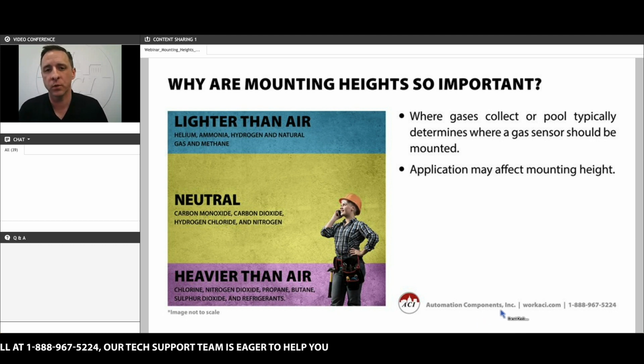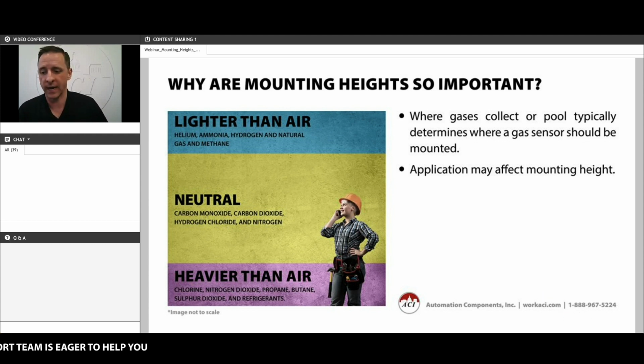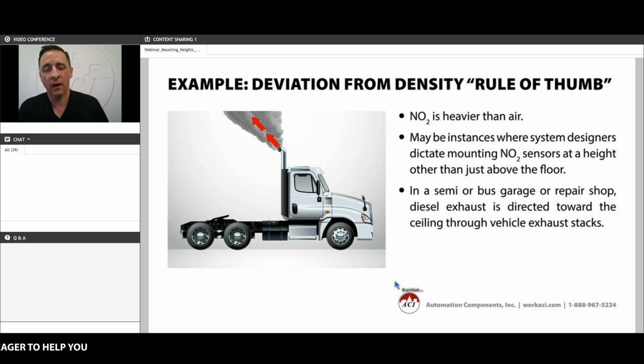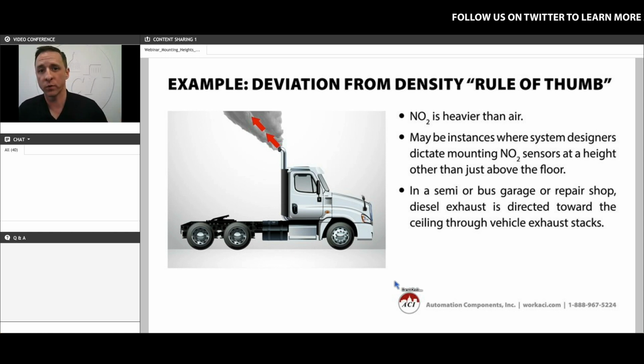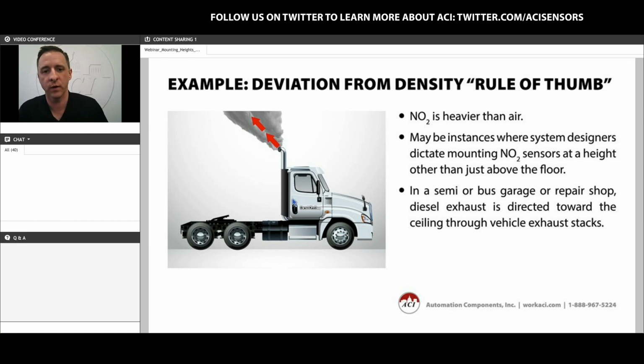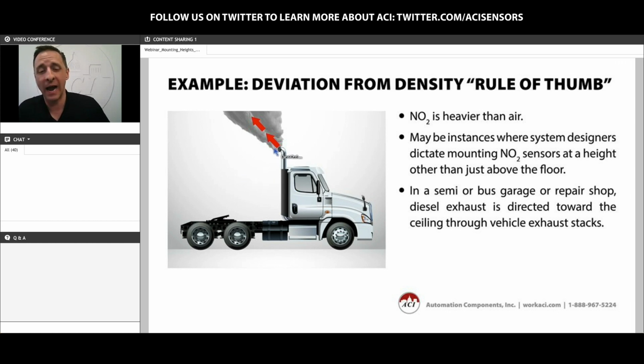However, there are certain applications that we come across pretty regularly where you might want to mount a sensor in a different spot than what's based on the chemical density of that particular gas, and we'll discuss that right now. For NO2 gas, or nitrogen dioxide specifically, it's present in diesel exhaust. So we're seeing requirements for parking garages, bus garages, loading docks, fire stations, and bus stations, where you have to monitor both CO gas, carbon monoxide, and NO2, nitrogen dioxide. So in those applications you might have a high stack exhaust, like you see in the semi pictured here on your screen, where that gas is going to be exhausted up high towards the ceiling.